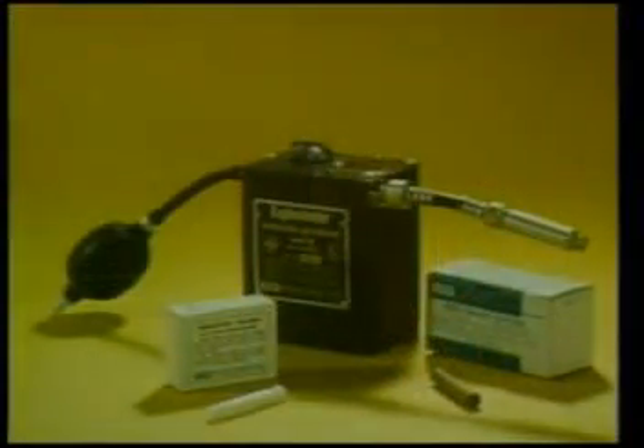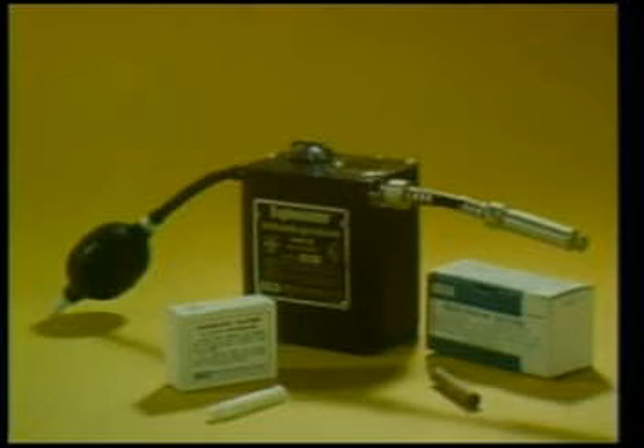If leaded gasoline vapors are present, an inhibitor filter must be used to protect the filament from lead deposits. A charcoal filter in a cartridge holder absorbs organic vapors and helps distinguish between gases in the sample and vapors that may cause condensation in the sampling system.